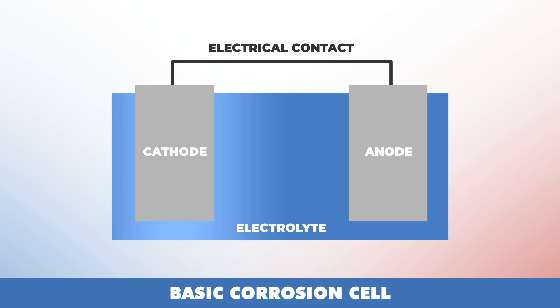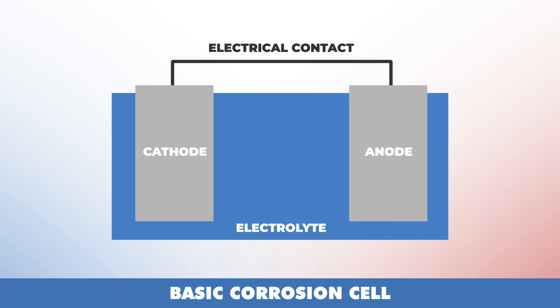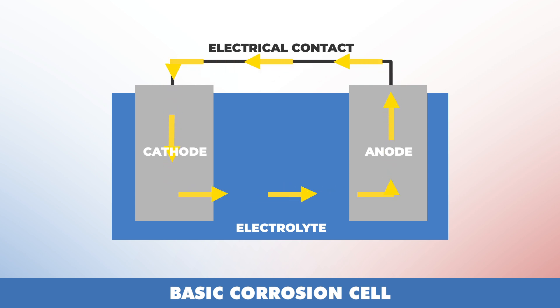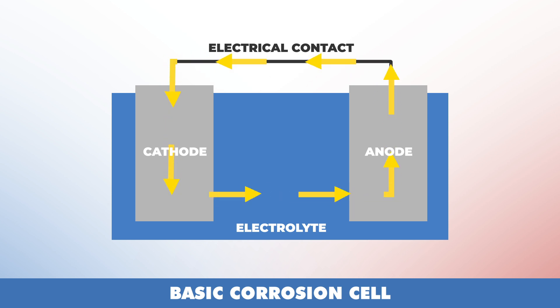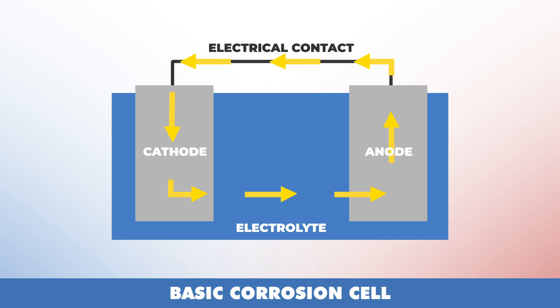An electrolyte is a substance with low electrical resistivity that surrounds the anode and cathode. When the cell is complete, there is an electrical current flow from the anode to the cathode. This happens because the anode and cathode are two different metals that require different amounts of energy to be processed from ore. They present each other with an energy difference, or an electrical potential difference. When the current flows, it causes corrosion damage to the anode.